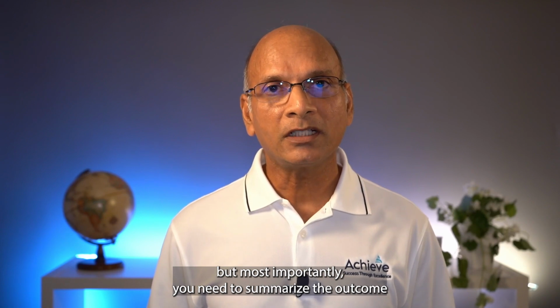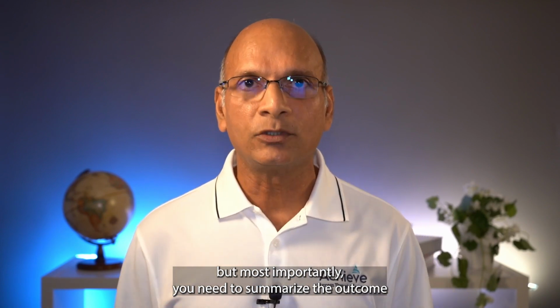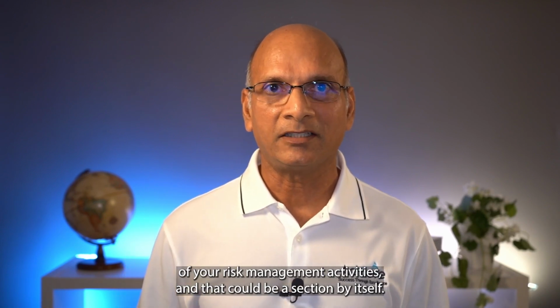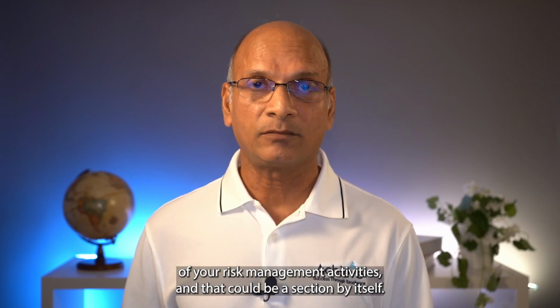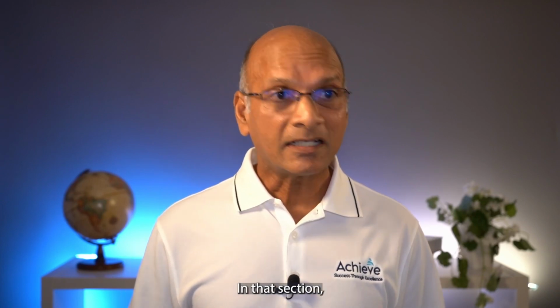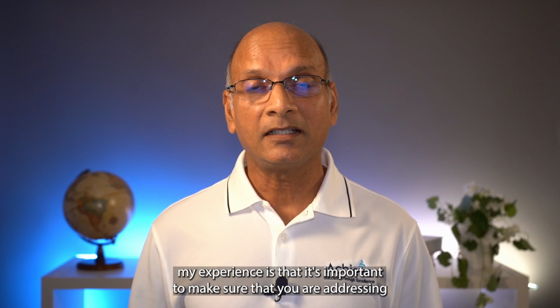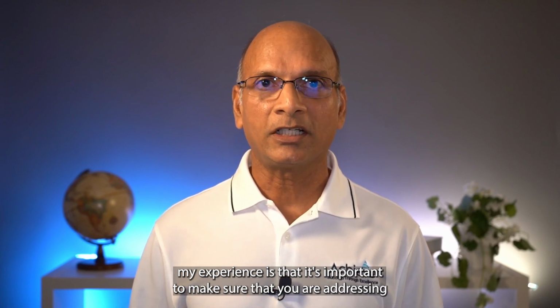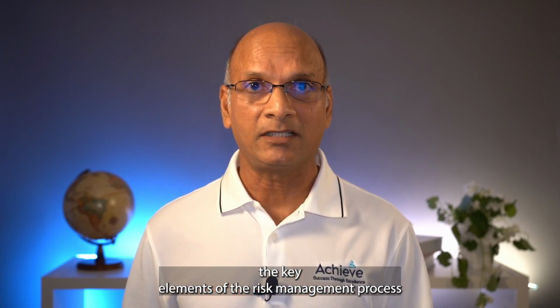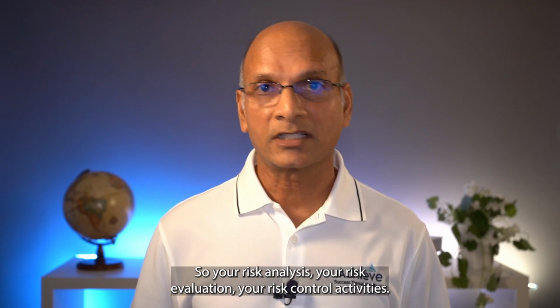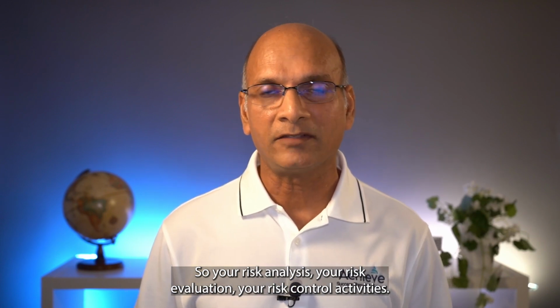But most importantly, you need to summarize the outcome of your risk management activities, and that could be a section by itself. In that section, my experience is that it's important to make sure that you are addressing the key elements of the risk management process as outlined in ISO 14971. So your risk analysis, your risk evaluation, your risk control activities.